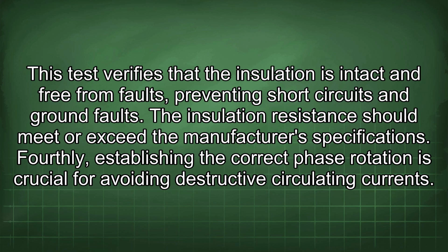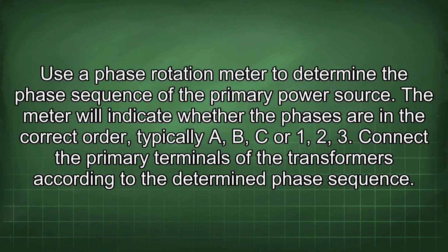Fourthly, establishing the correct phase rotation is crucial for avoiding destructive circulating currents. Use a phase rotation meter to determine the phase sequence of the primary power source. The meter will indicate whether the phases are in the correct order, typically A, B, C or 1, 2, 3.